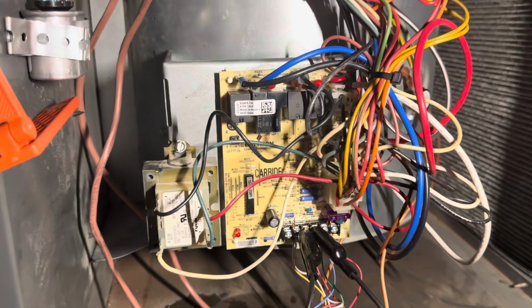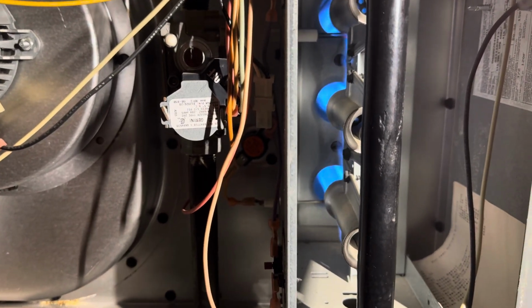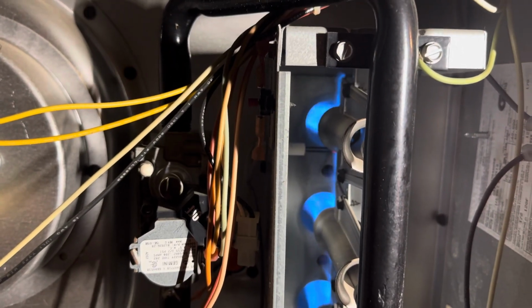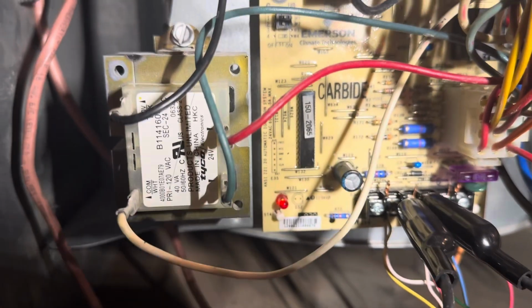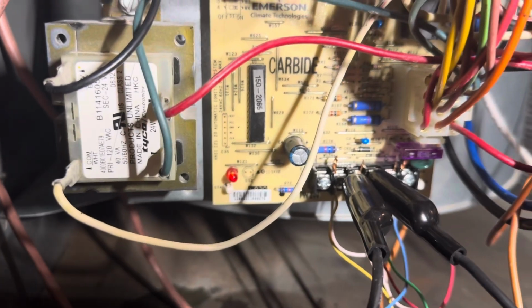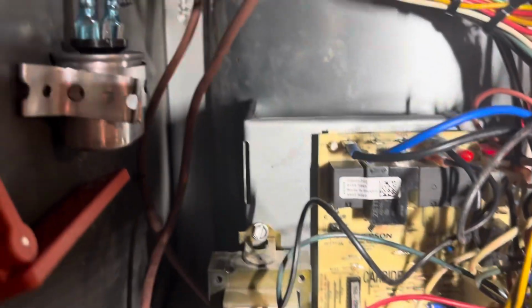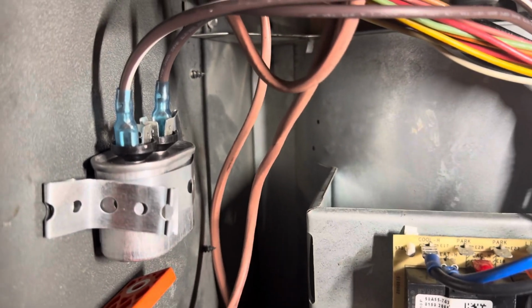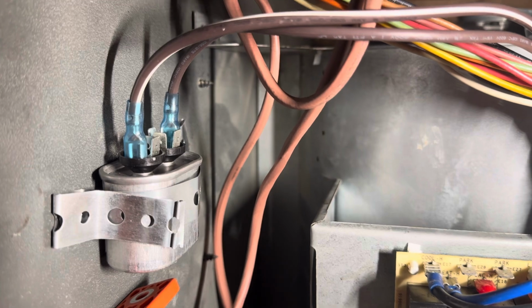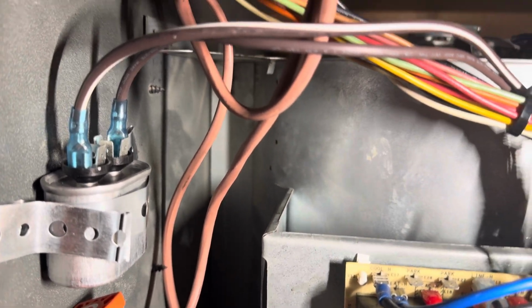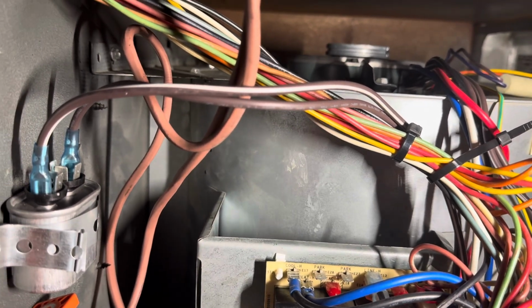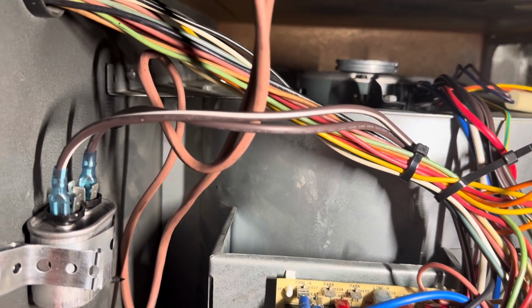So hopefully that gives you a good overview of the sequence of operations of a gas furnace. Again, we talked about some points with the flame rod. It could be dirty. The igniter could be faulty if it cannot come on. I talked about here, if we don't have a light on the control board, it could be the transformer, it could also be a blown fuse, which is typically indicative of a wiring issue as well. And up here, I didn't really address this exactly, but this is an older motor. It's called a PSC, a permanent split capacitor motor, the blower motor up there. And if that capacitor is bad, the blower motor will not start.